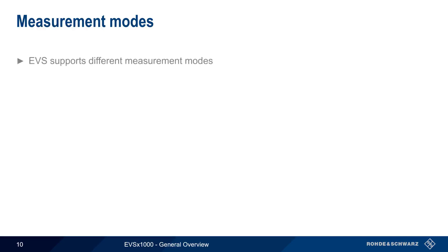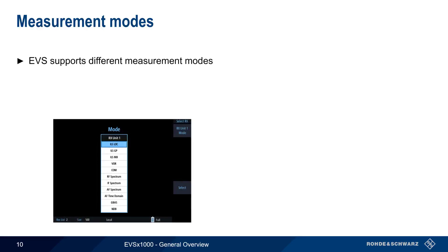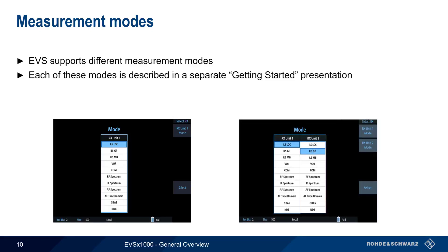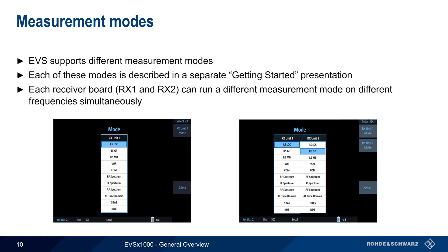Regardless of how the instrument is accessed, the EVS1000 is always operated in one of the available measurement modes. These modes include NAVAID and COM-specific modes such as ILS, VOR, GBAS, etc., as well as more general analysis tools such as RF or AF spectrum or AF time domain analysis. Each one of these different modes is described in detail in a separate Getting Started presentation. For EVS models that contain two receiver boards, a different mode can be chosen for each board, and these modes can be run simultaneously on different frequencies, although measurement results are displayed one board at a time.